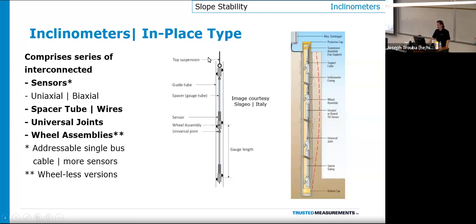They typically comprise a series of interconnected sensors, both uniaxial and biaxial, depending on what you're trying to measure. They come in different lengths. So as I mentioned, a manual sensor takes measurements every 2 feet, every half meter. These typically come in 0.5, 1, 2, 3 meter, and then 2, 5, and 10 foot segments, basically. And you can orient them in any way, shape, or form.